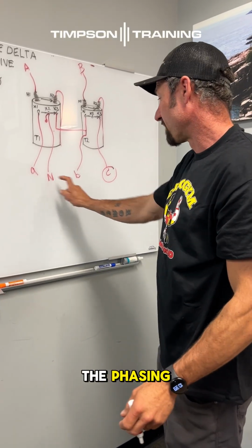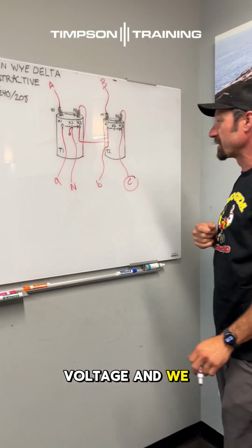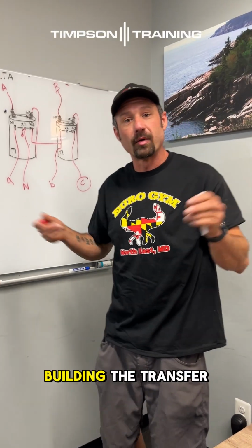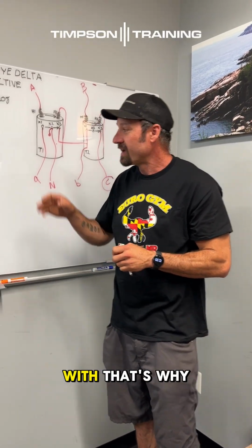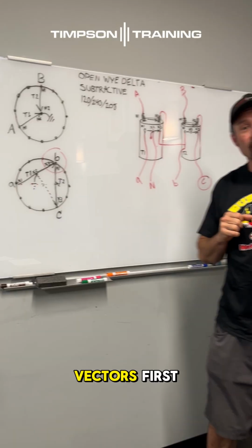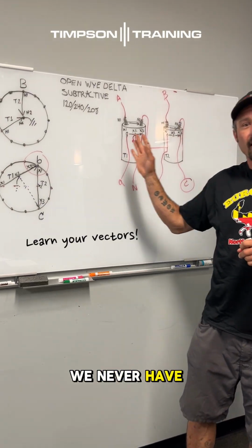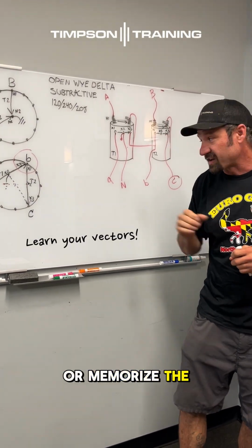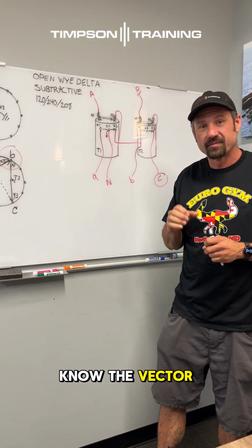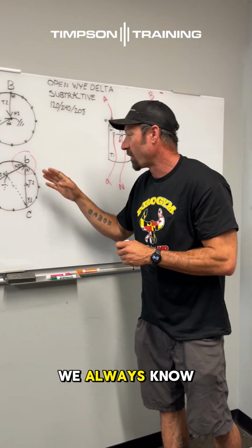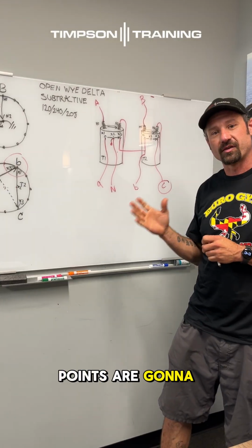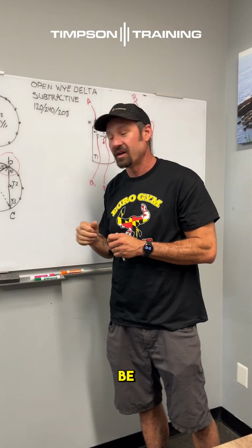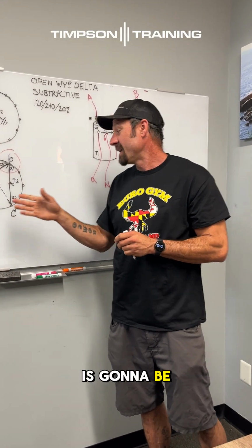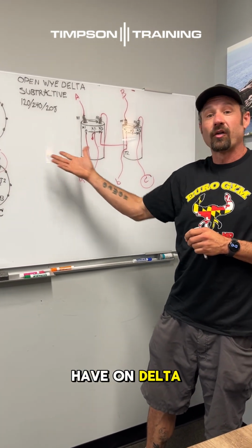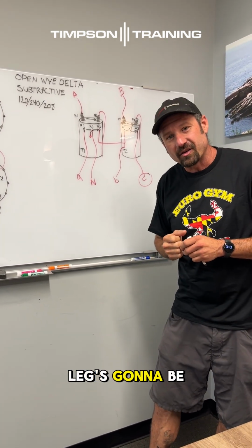And we know the phasing, we know the voltage, and we know where the high leg is prior to ever building the transformer bank to begin with. That's why if we learn vectors first, we never have to learn connections or memorize the connections, because we know the vector, we've memorized the vector, and we always know where the connection points are going to be, what the phasing is going to be, what the rotation is going to be, and if we have a delta with a high leg, we know right where the high leg is going to be.